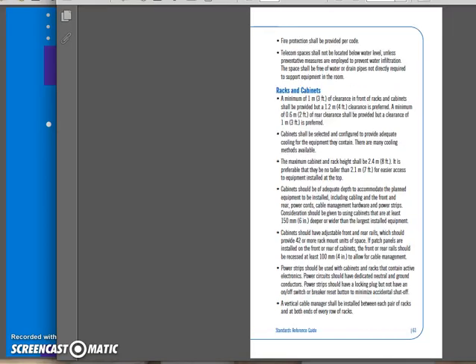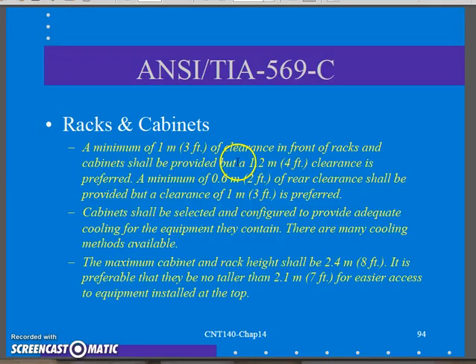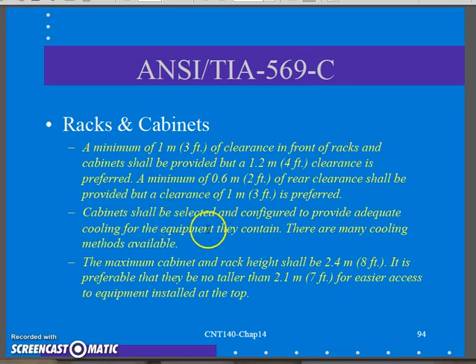The next area of the standard talks about racks and cabinets. They talk about a minimum amount of clearance in front of the rack — the idea is I should be able to get the door open and get switches and equipment in and out. Think about a rack-mount server: there needs to be enough room to slide it out, work on it, and slide it back. They're talking about minimum clearance in front and minimum clearance behind as well.